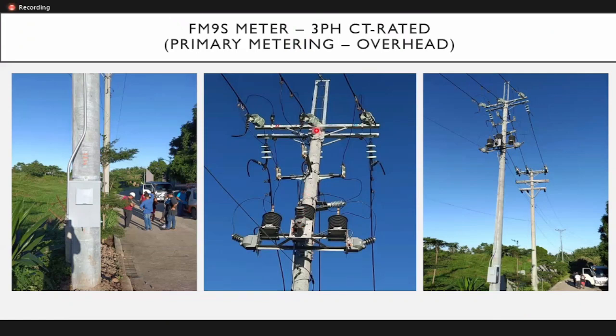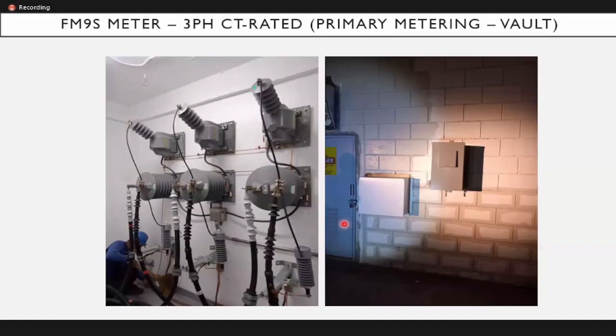This is a typical installation of primary metering overhead. So inside this box is the Form 9S. The primary metering, this is the primary metering PT, and this is the primary metering CT overhead. This is the primary metering vault type. So inside here is the Form 9S meter. This is the primary metering PT, and this is the primary metering CT.